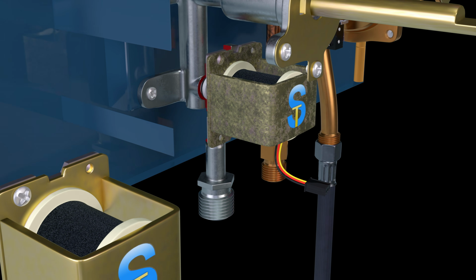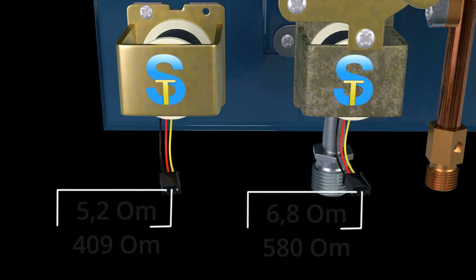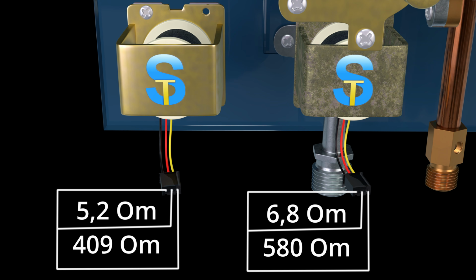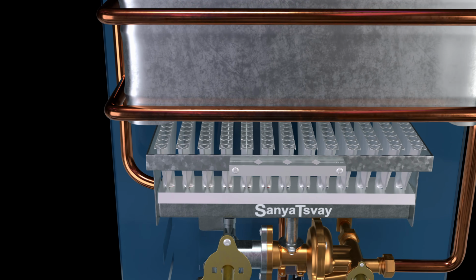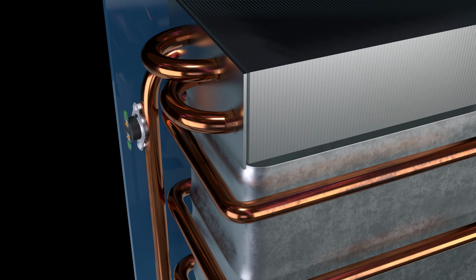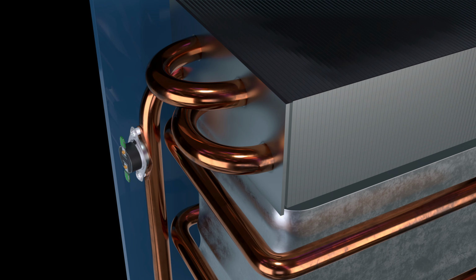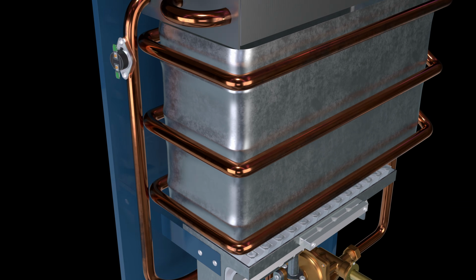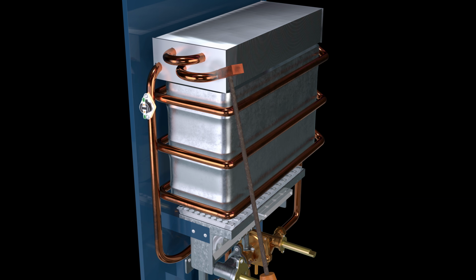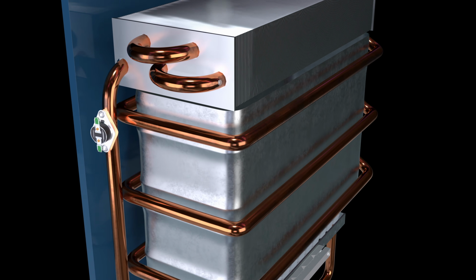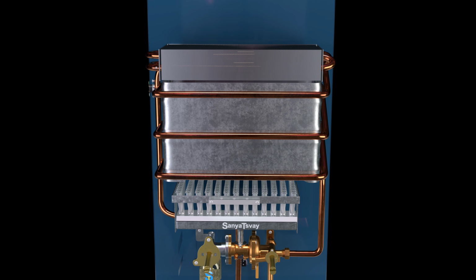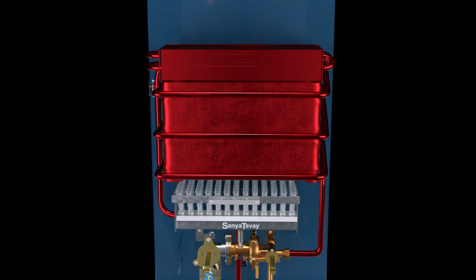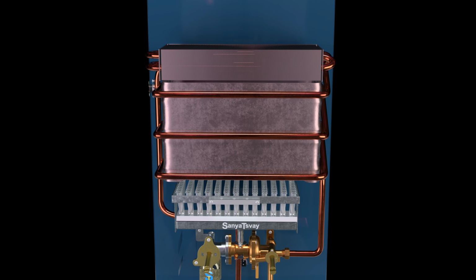I'm including the resistance measurements of both solenoid coils. On the right is the working one, and on the left, the one that didn't function properly. The difference in resistance doesn't seem large, but it was enough to affect its operation. And the last malfunction, a leak in the heat exchanger. I disassembled it, found the spot where it was leaking, and soldered it with tin. This repair lasted for about 3 years, until a new leak appeared, this time in a place where you simply can't reach with a soldering iron. I didn't think too long about it. I installed a new heat exchanger. With the new one, the heater has been working ever since, without any issues.